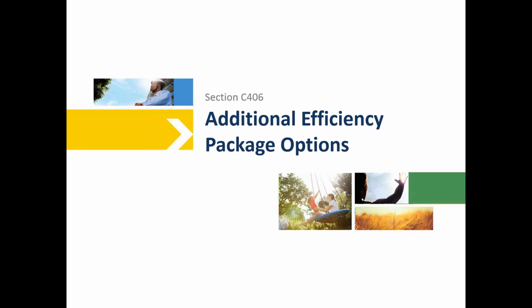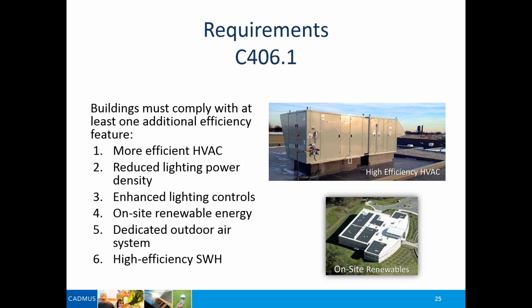So to get additional savings, we have this provision where, in addition to all the minimal provisions you've complied with, there's one more to comply with, and we can see them on the next slide. And there we go. You only need to select one of these. We've got a lot of HVAC people in the audience today. That's a no-brainer. Just go up a couple of SEER, and incidentally, on the residential arena, the code specifies a 14 SEER for residences, and there is in town at a fairly reasonable price a residential unit with 32 SEER. So at the commercial level, I don't think there's anything that dramatic, but that would be pretty easy to comply with.